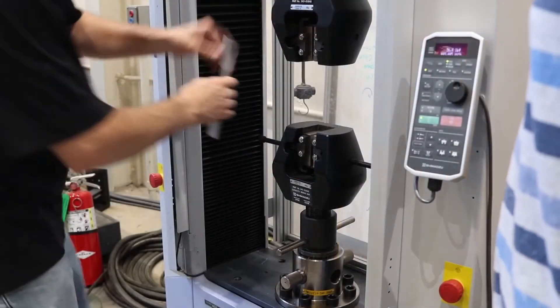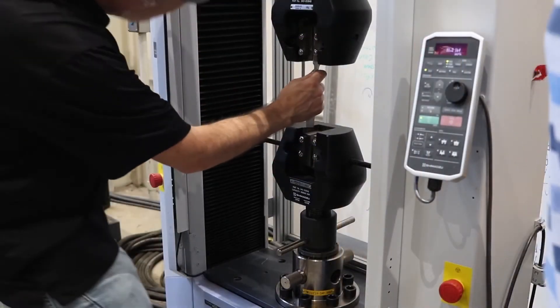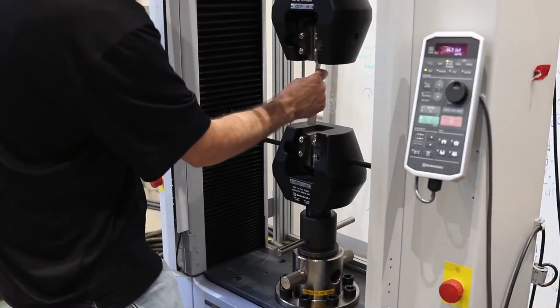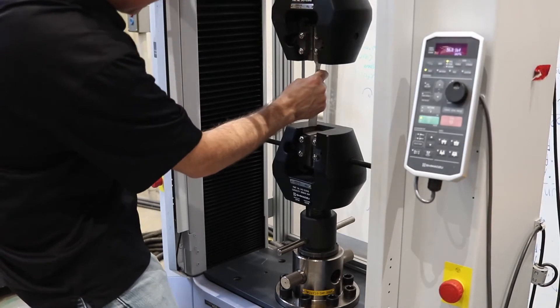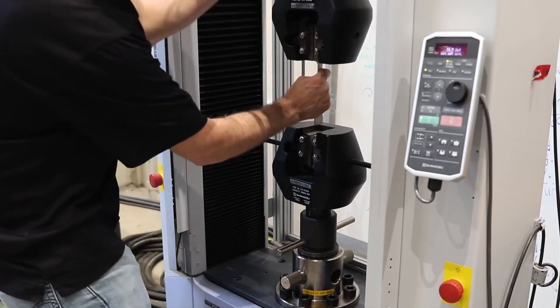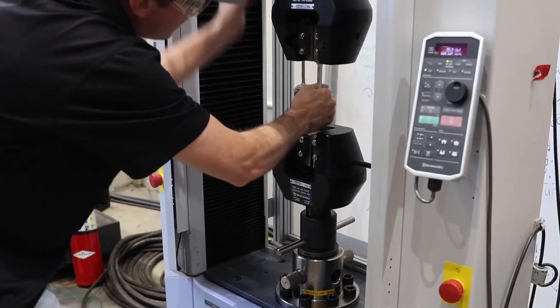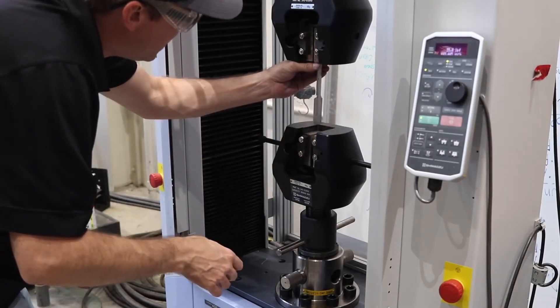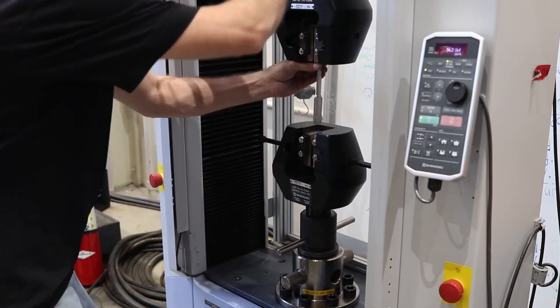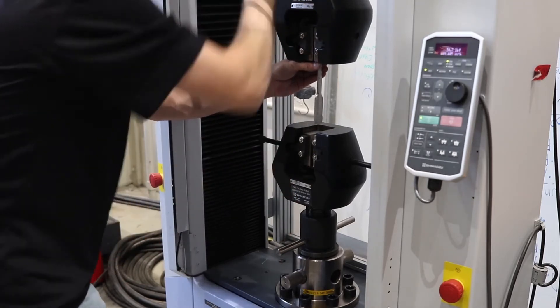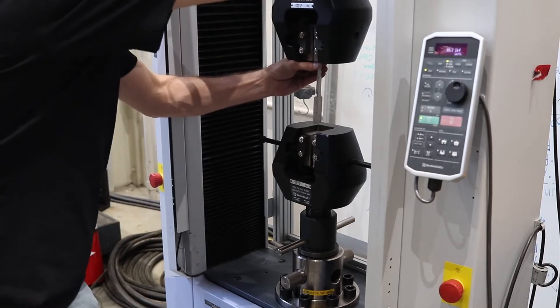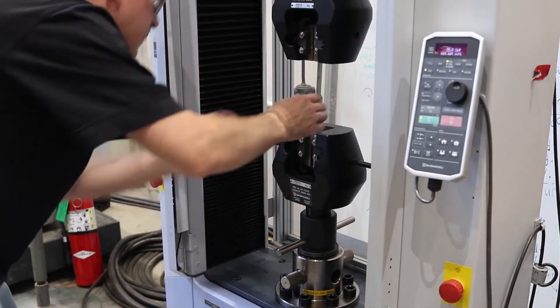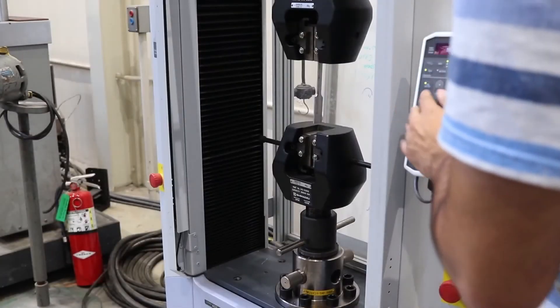Now we install the dog bone in the jaws. We place the specimen in the upper jaws first, aligning it correctly so it is perpendicular to the face of the jaw. The top of the sample should roughly align with the scribe in the jaw face. After aligned, we tighten the upper jaw. This process is much more easily completed with two students.